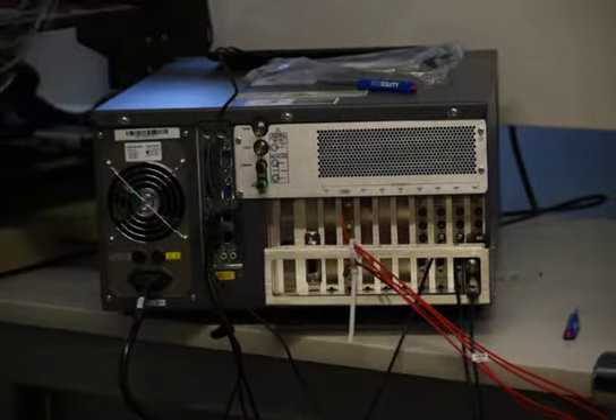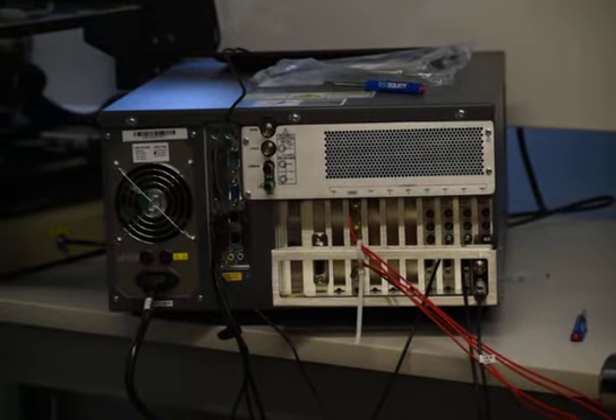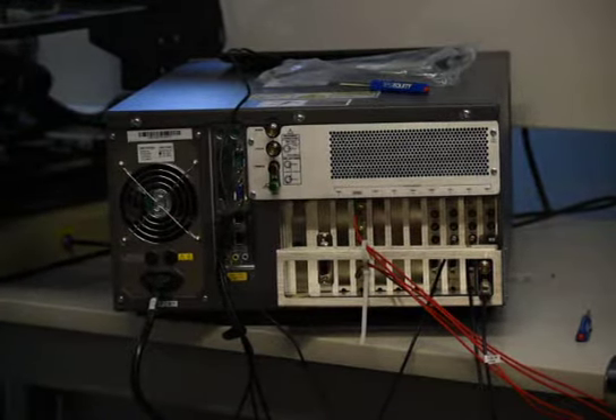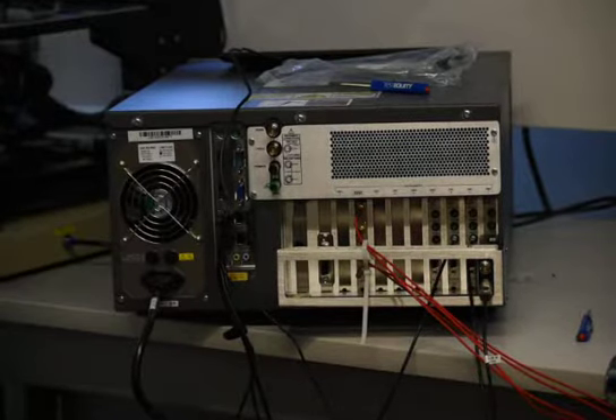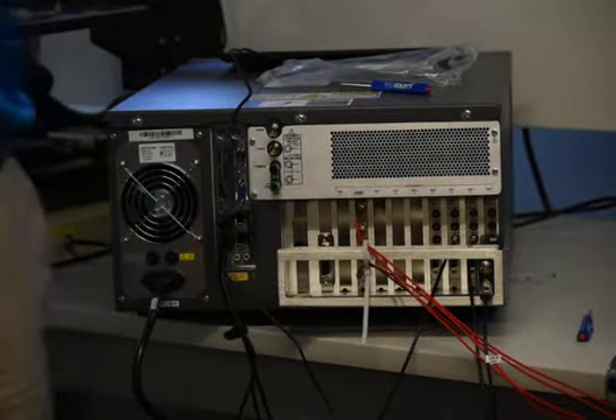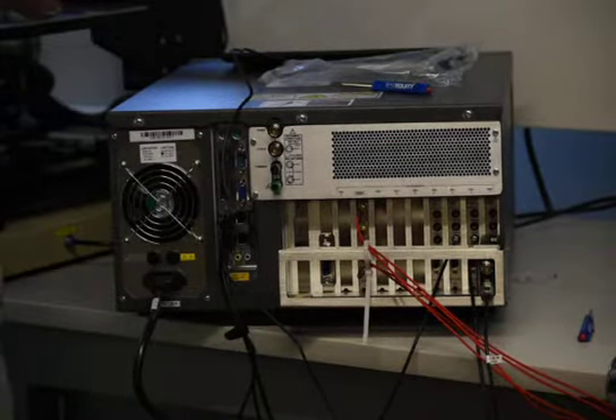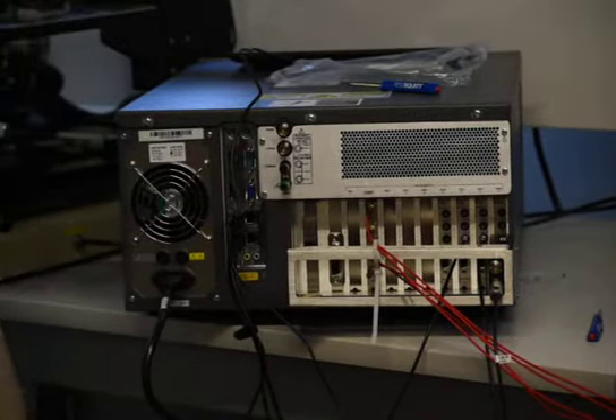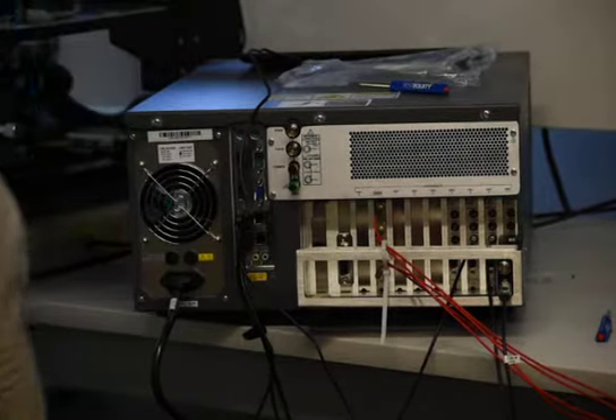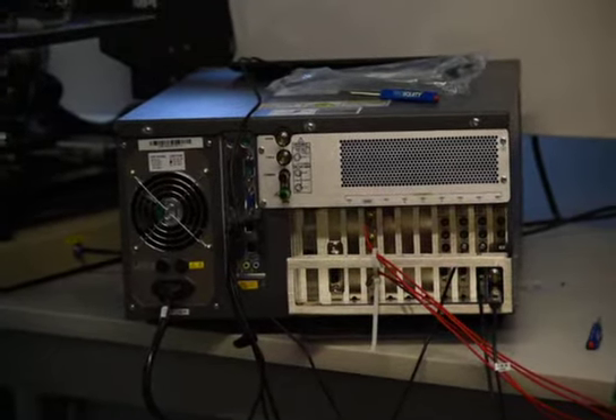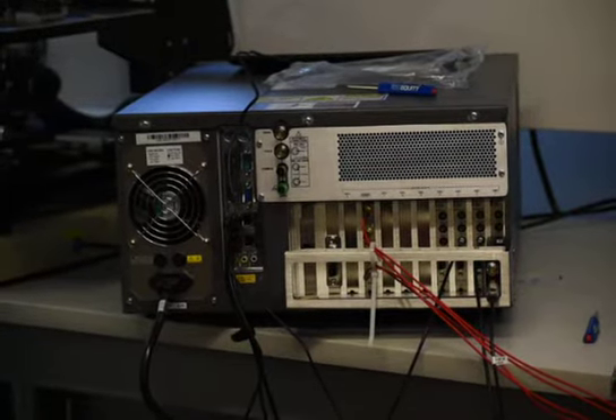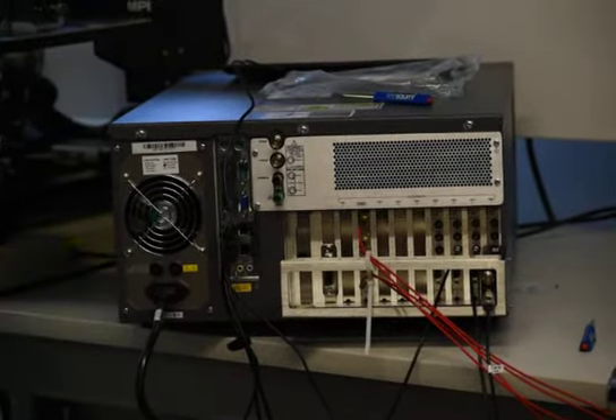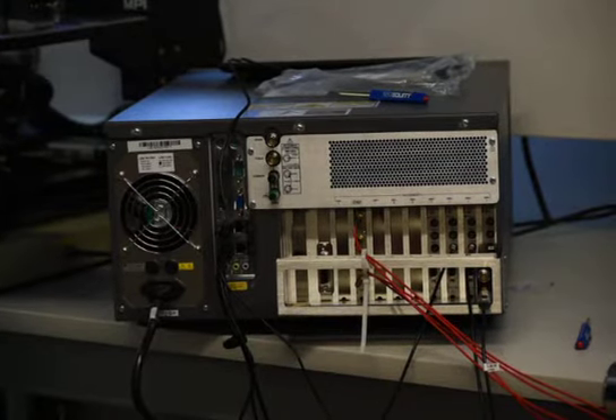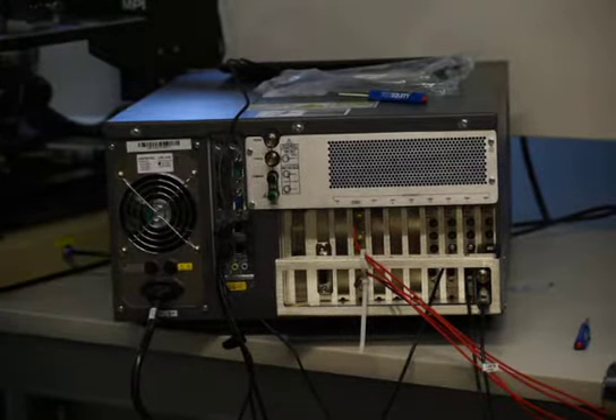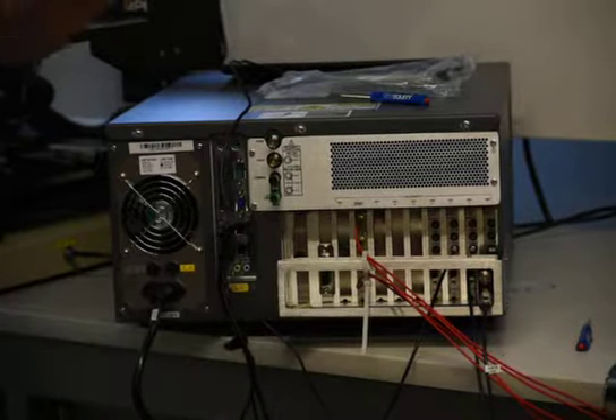One thing I want to warn you about is an SMU has very high input impedance. It's 10 to the 14, 10 to the 18, a big number. What I'm trying to get at is off does not mean off necessarily. When the SMU is off, people think it's safe to grab the device and unplug it. If your device has capacitance, this is not going to discharge it, because the impedance is so high, you could have a charge on your device for quite a while after you turn off the SMU. So just be aware: off does not mean off when you talk about SMUs.